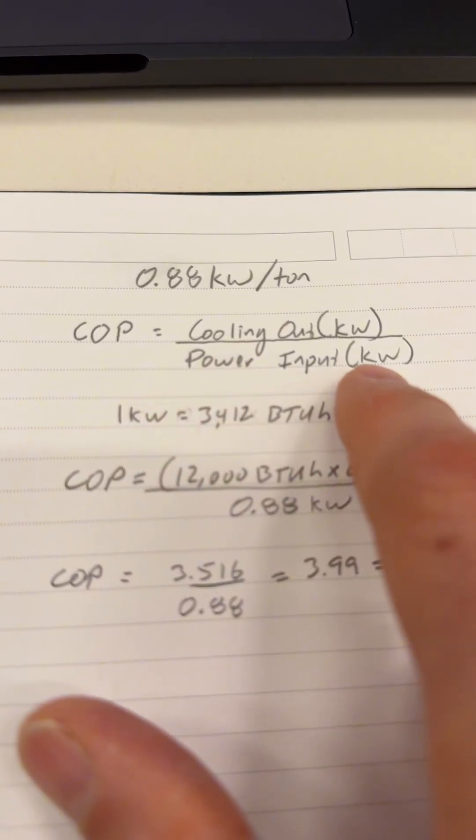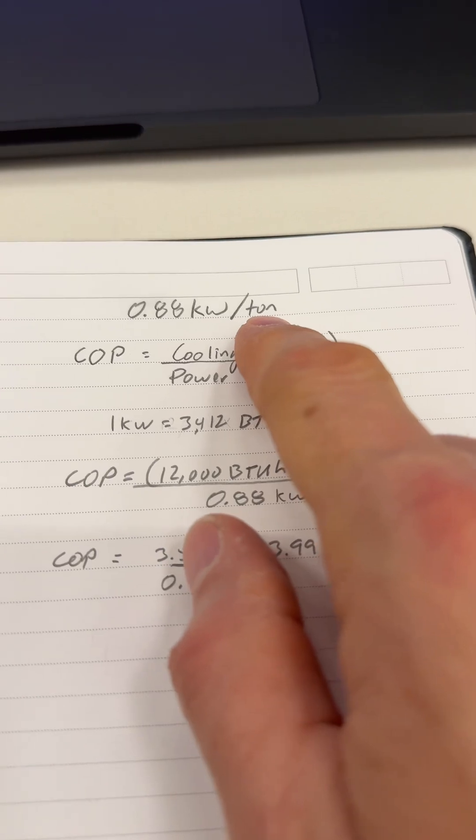COP is calculated as the cooling output in kilowatts divided by the power input in kilowatts. We know the power input is 0.88 kilowatts, and the output is a ton, so we have to convert the tonnage to kilowatts.